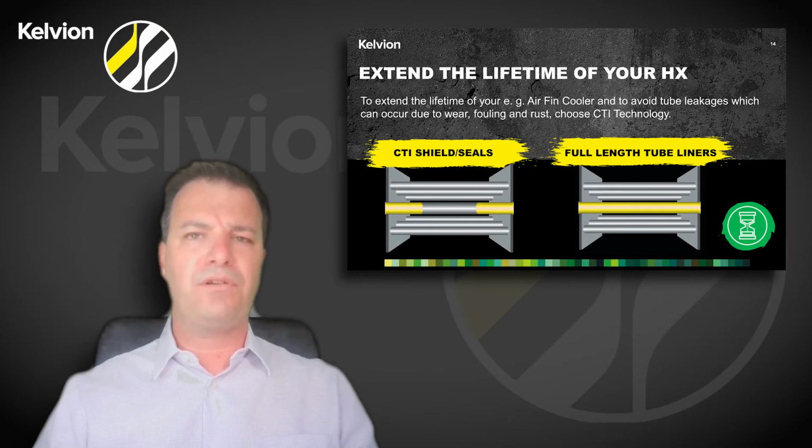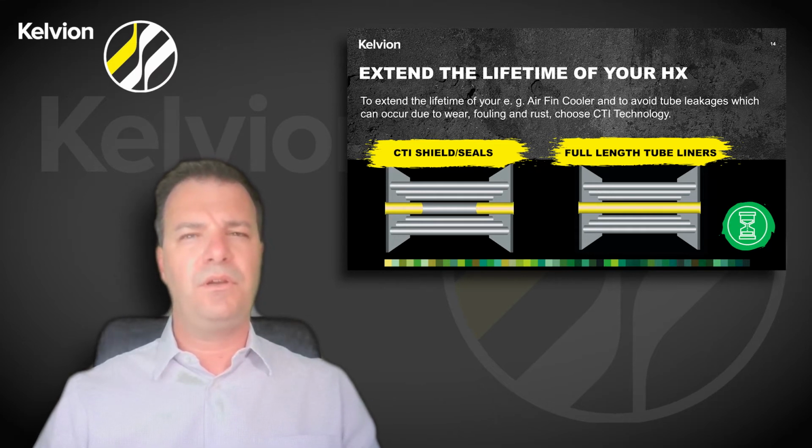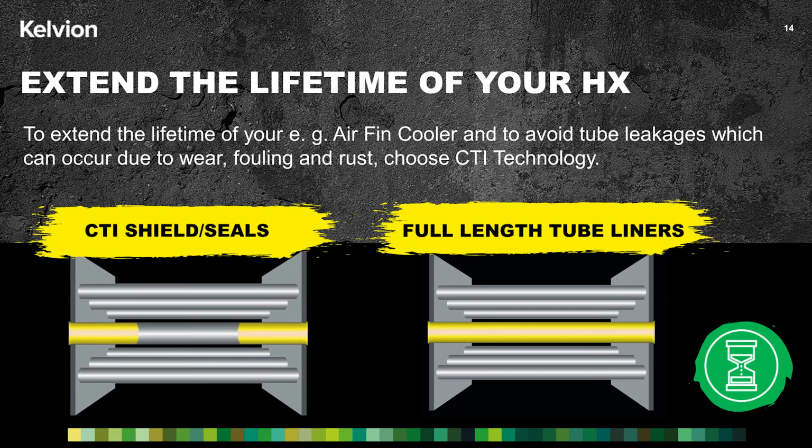This technology repairs damaged and or leaking tube ends, including tube-to-tube sheet weldings, and prevents unnecessary retubing or plugging, instead of replacing the entire tube when only the first 20 or 30 centimeters are worn. It also repairs or restores tubes suffering from corrosion with full-length liners as shown above. The installation is done using two different methods, either mechanical expansion or CTI's full-length hybrid expansion.